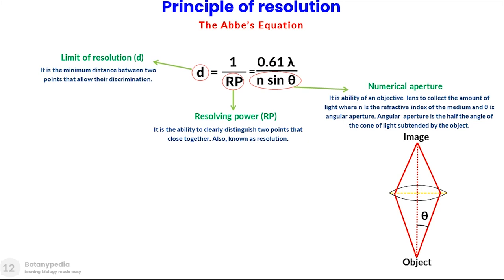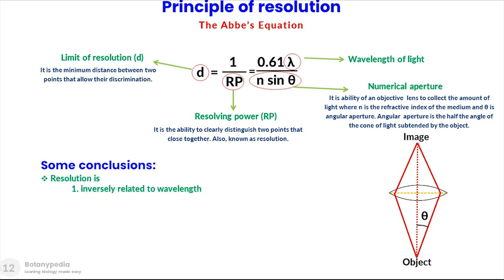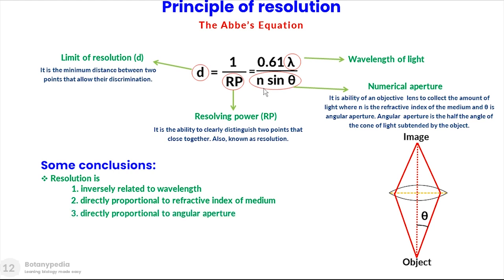It is important to mention that n is the refractive index of the medium and it greatly influences the resolving power of the microscope. The angular aperture is defined as half the angle of the cone of light subtended by the object. Lambda refers to the wavelength of light used for illumination. From this equation we can conclude that resolving power is inversely related to wavelength of light, directly proportional to the refractive index of the medium, directly proportional to the numerical aperture, and inversely related to the limit of resolution.